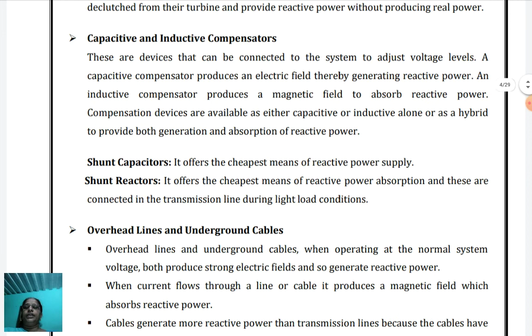Compensation devices are available as either capacitive or inductive alone, or as a hybrid combination of inductive and capacitive reactance, to provide both generation and absorption of reactive power. That means the capacitive and inductive compensators can be used for both generation and absorption of reactive power. Next component is shunt capacitors and shunt reactors. Shunt capacitors offer the cheapest means of reactive power supply. Shunt reactors offer the cheapest reactive power absorption, and they are connected to the transmission line during light load conditions only.